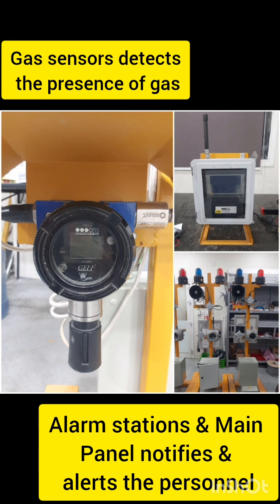So the alarm station will notify or alert using the siren, the horn to make a sound, and also the visual lights. There is a toxic light which is blue or amber, and then there is a flammable, combustible or LEL light which is the red color.